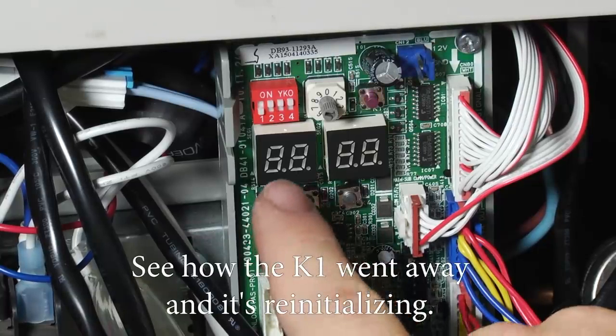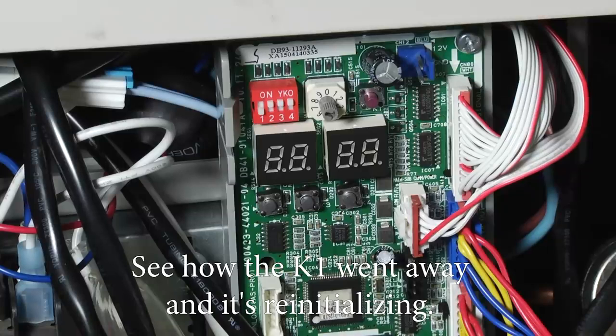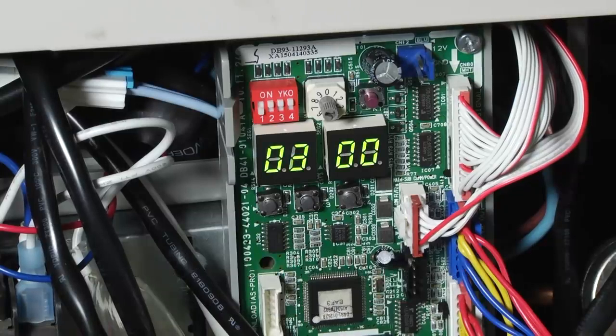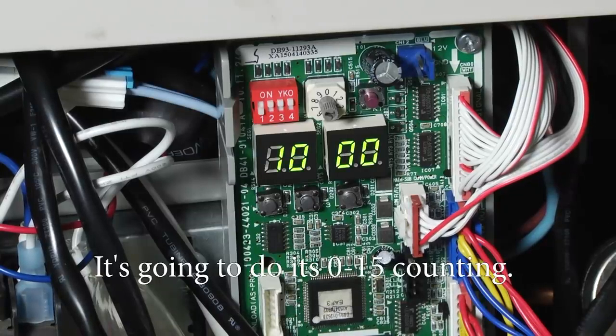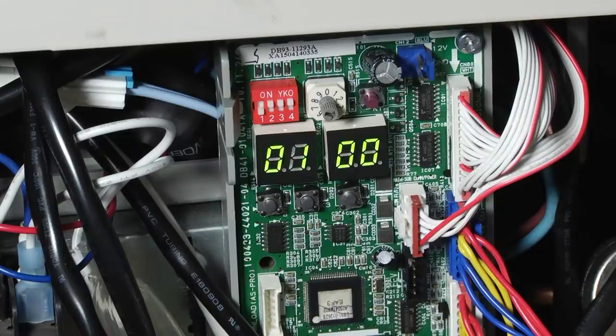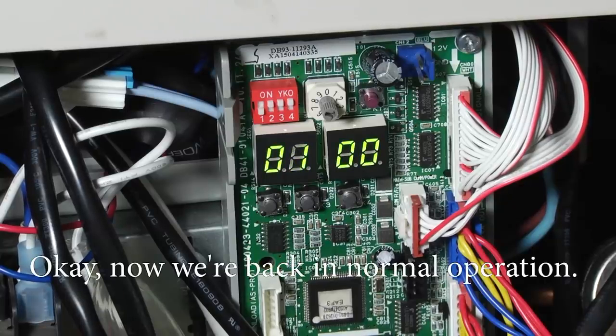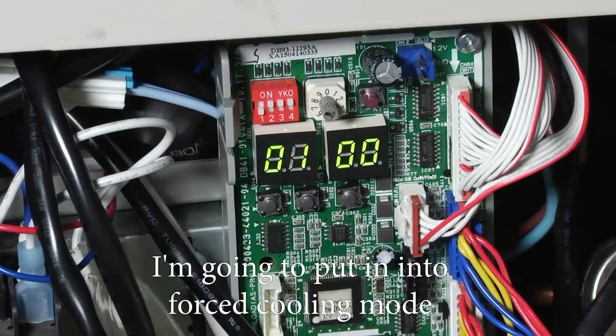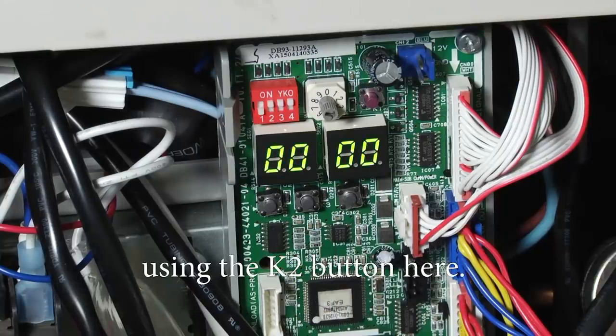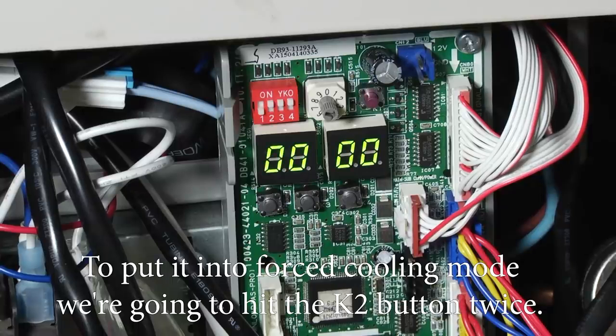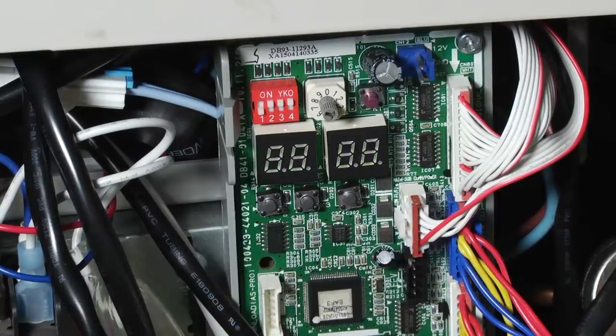See how the K1 went away? And it's reinitializing. It's going to do its 0 through 15 counting. Okay, now we're back in normal operation. I'm going to put it into force cooling mode using the K2 button here. To put it into force cooling mode, we're going to hit the K2 button twice.